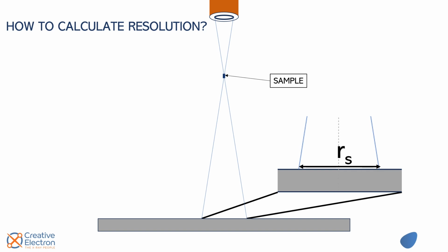And the resolution of the source we call RS, which is this distance here, the overall penumbra onto the detector. Now, it's not going to be exact. There are some other factors that have to be taken into consideration. For example, the flux out of the X-ray source is not constant. We're assuming that it's constant here, but it's not, so there are fewer photons on the edges of the beam than in the center of the beam, because it's a cone beam shaped flux coming out from the X-ray source. But for now, let's consider it a constant so that we can go through this calculation.